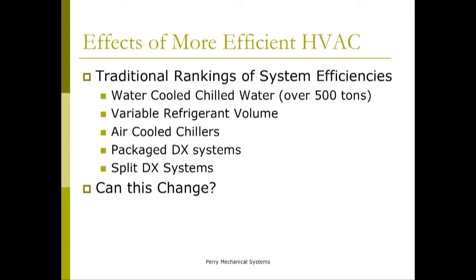That needs to be analyzed more if you're looking at a life cycle analysis of 25 plus years, especially in our environment, because air-cooled equipment sits outside and won't always last as long as water-cooled equipment. If you factor in the cost of changing out an air-cooled chiller versus not having to change out a water-cooled one, it can make sense to go water-cooled at much smaller tonnages as well.